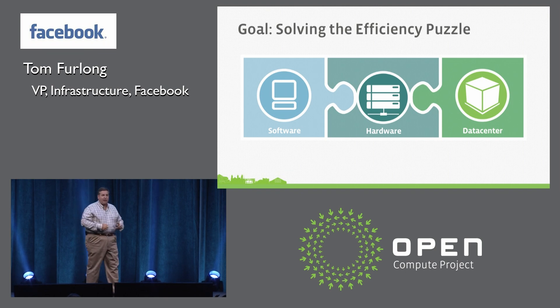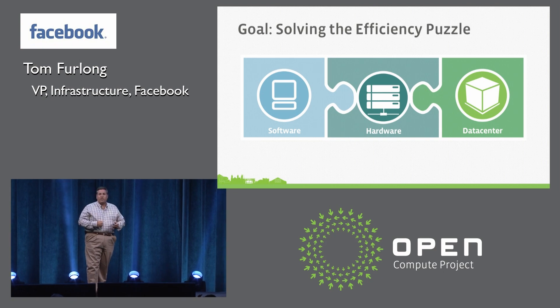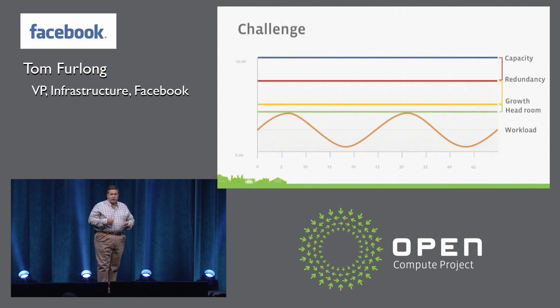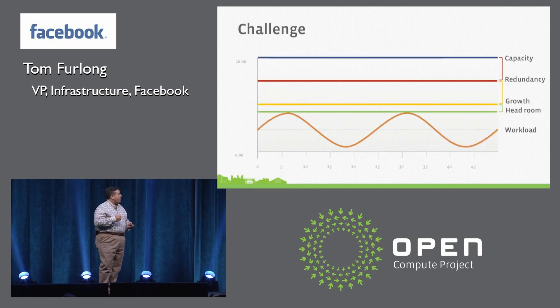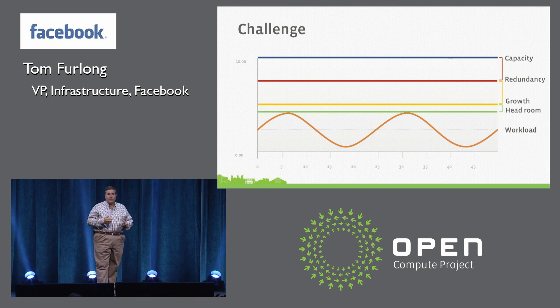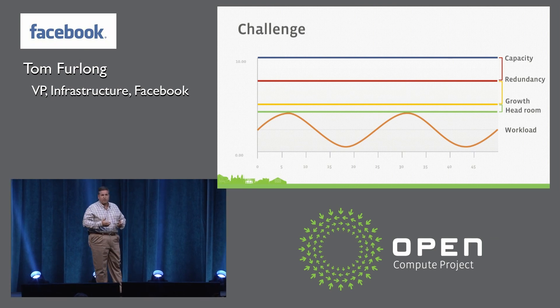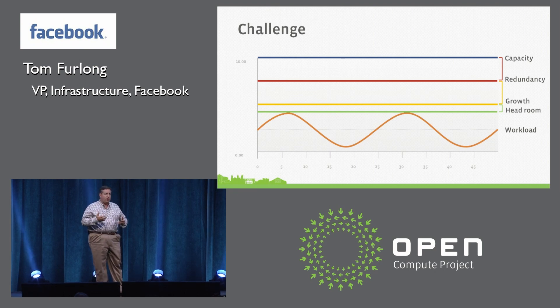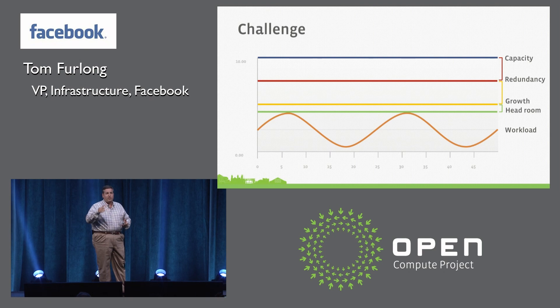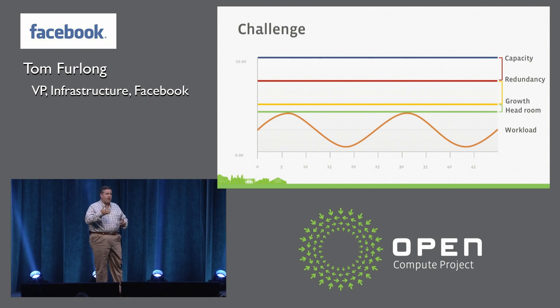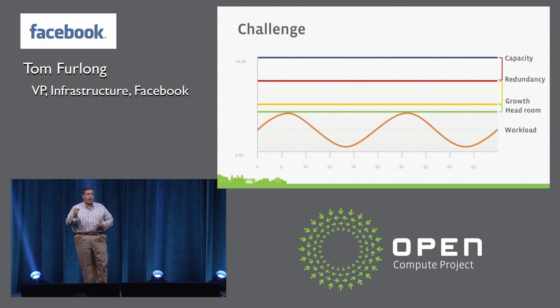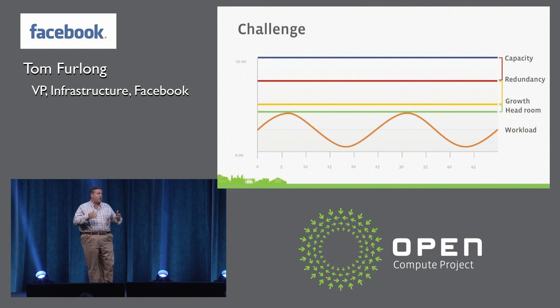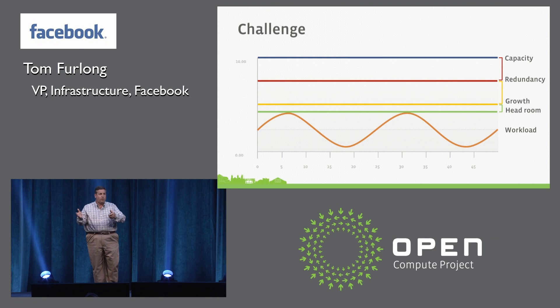This gets into a capacity question: how do you put as much hardware into the data center as you can with a reasonable level of risk tolerance? You've got fixed capacity — a certain amount of electrical capacity in the system itself. You also have a workload, and for us our workload looks rather sinusoidal. We have peaks of the day and peaks of the week. We also have a regional failover model, so we reserve some capacity so that if a region has a problem, we can fail the traffic out of that region and distribute it across our other regions.